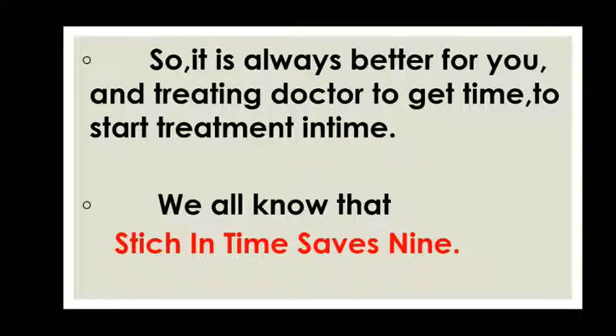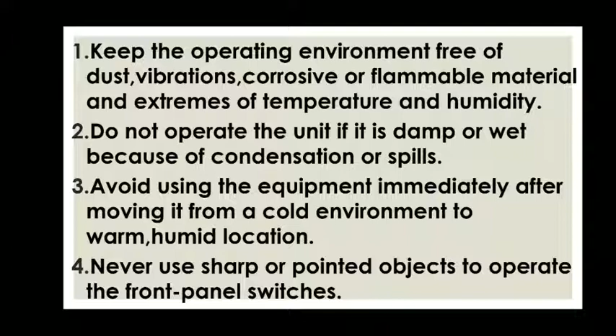So which cautions and how to maintain the life of the device? Keep the operating environment free of dust, vibrations, corrosive or flammable material and extremes of temperature and humidity. Do not operate the unit if it is damp or wet because of condensation or spills. Avoid using the equipment immediately after moving it from a cold environment to a warm or humid location. Never use a sharp or pointed object to operate the front panel switches. The batteries must be taken out from the battery compartments if the device will not be in use for a long time. The device shall only be used if the battery cover is closed. The batteries must be properly disposed of according to local regulation after their use.